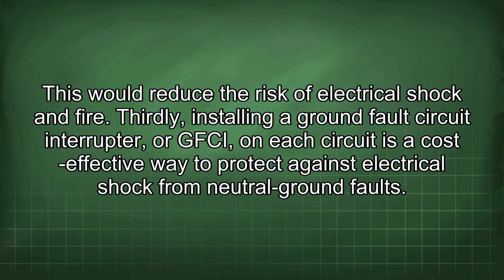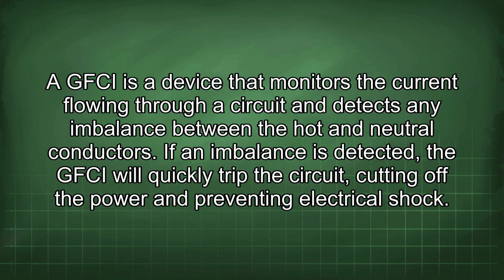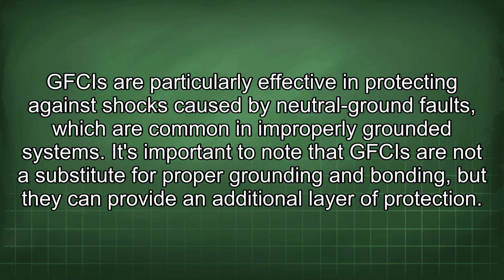Thirdly, installing a ground fault circuit interrupter, or GFCI, on each circuit is a cost-effective way to protect against electrical shock from neutral ground faults. A GFCI is a device that monitors the current flowing through a circuit and detects any imbalance between the hot and neutral conductors. If an imbalance is detected, the GFCI will quickly trip the circuit, cutting off the power and preventing electrical shock. GFCIs are particularly effective in protecting against shocks caused by neutral ground faults, which are common in improperly grounded systems. It's important to note that GFCIs are not a substitute for proper grounding and bonding, but they can provide an additional layer of protection.